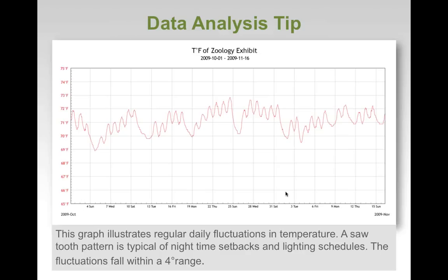One of the things I discussed earlier in the presentation was being able to see occupancy in a graph. When you see a sawtooth graph similar to this, it's a pretty fair sign of occupancy's influence. If you were looking at this graph, I like to use this section right about here. It's a great example of the occupancy, and you see it goes up about 3 degrees over the period of a week. This graph starts Monday, and this section right here ends on Sunday.